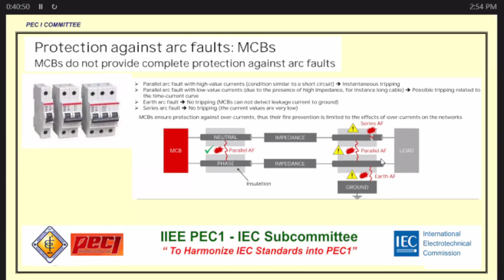So, protection against arc fault by miniature circuit breaker and molded case circuit breaker. I got this from ABB literature. Miniature circuit breakers do not provide complete protection against arc fault. If you look at it, the protection would be neutral to phase only, for the miniature. But if the current is too small, it would not be detected. So the miniature circuit breaker, or the molded case, cannot provide protection from arc fault.